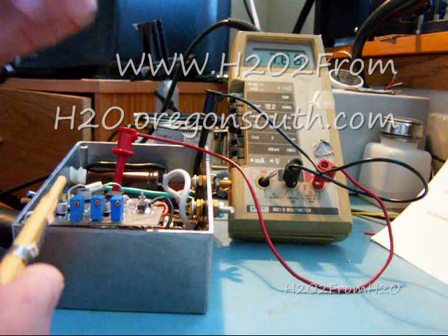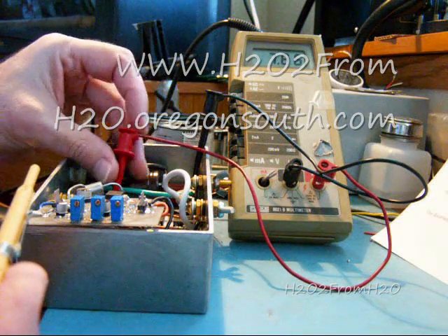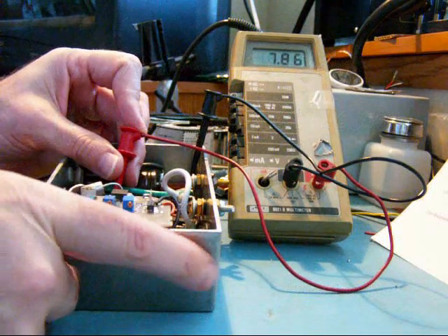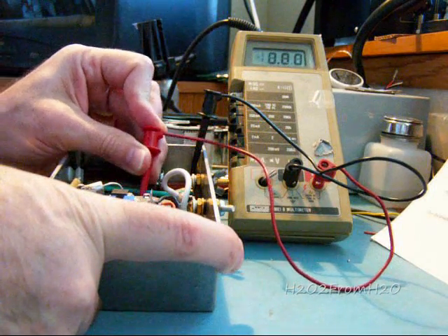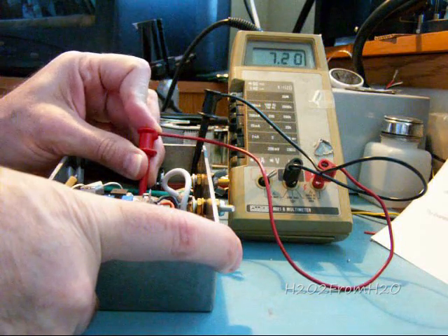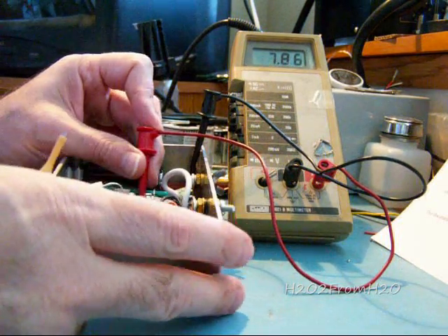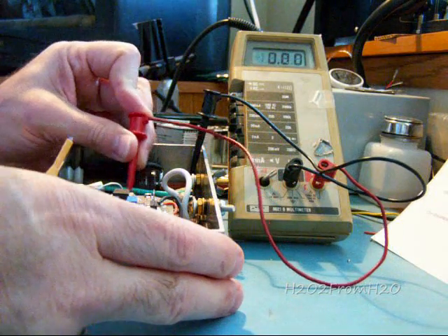Verify once you get it down a little bit, verify that gate A and B are the same voltage. So 7.86, 7.86. And there can be a slight variant in there, 10, 20 millivolts is fine.